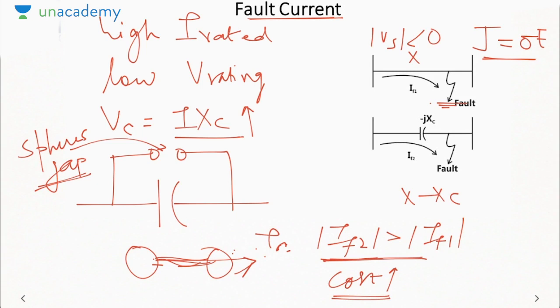So remember, the sphere gap will conduct only as long as the current is high. Once the fault is cleared, the current reduces, the air will deionize and the sphere gap will become insulating. So this is a kind of automatic switch. It will switch on when the voltage is high. It will switch off when the voltage becomes low. So current will conduct between the sphere gap by means of a spark or an arc.